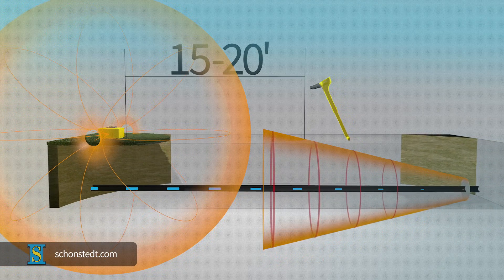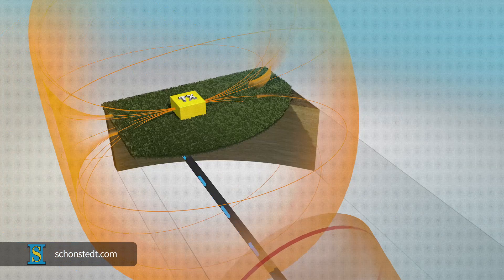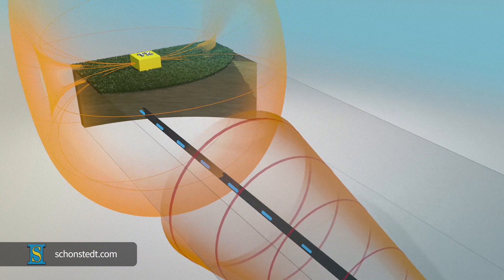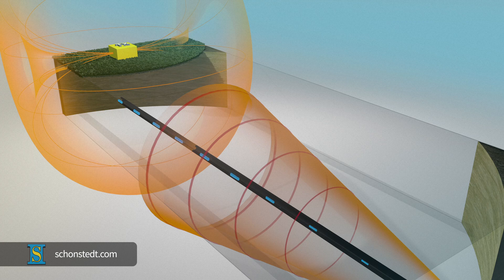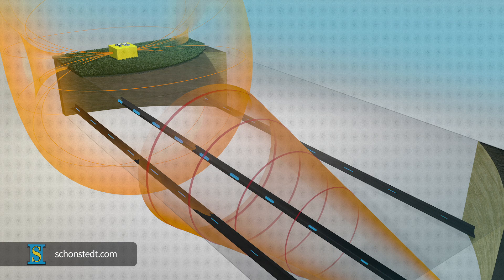If the transmitter isn't in the proper place, the signal is likely to be very weak. In addition, other nearby pipes or cables can complicate the locating process, because the signal will be induced in them as well.